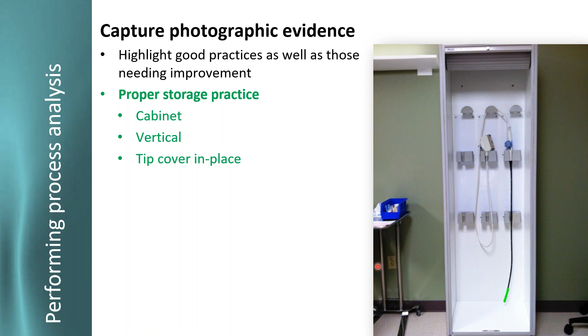Photographic evidence. You look at this particular cabinet here. This particular cabinet looks great. We've taken the strain off the main cable. We have the connector supported. There are no sharp bends. We're hanging the probe vertically, and you see this nice, lovely, bright green tip protector. So this is the proper way to store a TE probe.